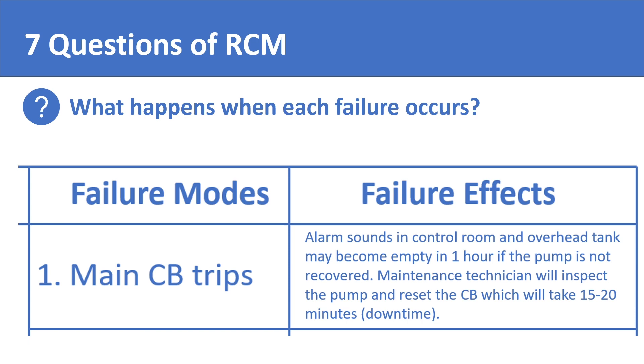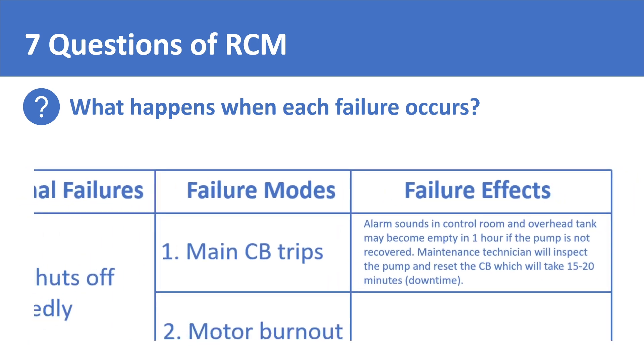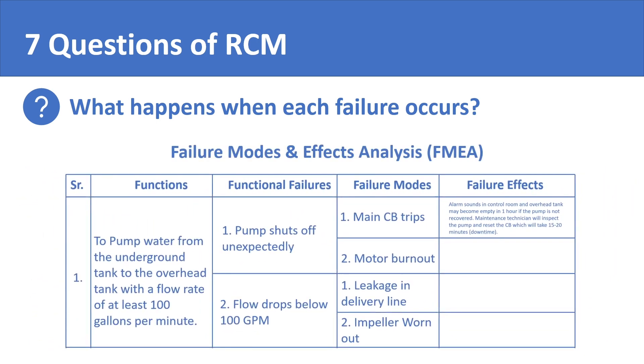When you complete this fourth step, what you have actually completed is a failure modes and effects analysis, or the famous FMEA. That is to say, the first four questions of RCM are actually a failure modes and effects analysis of your plant equipment.